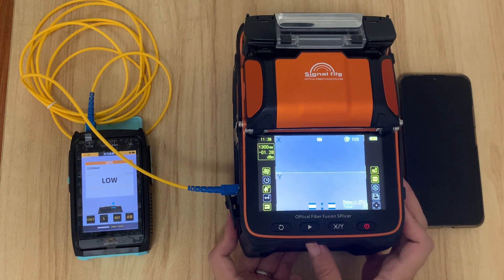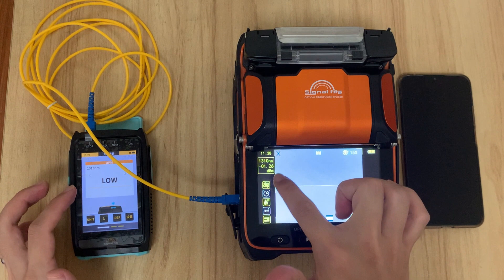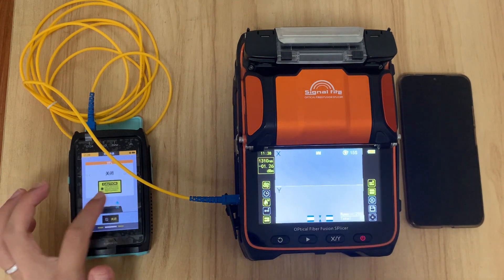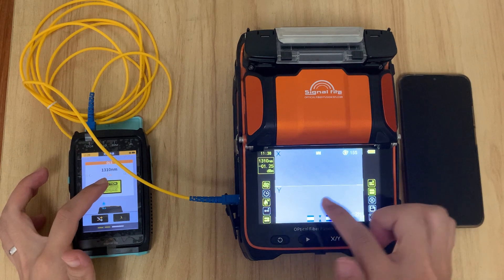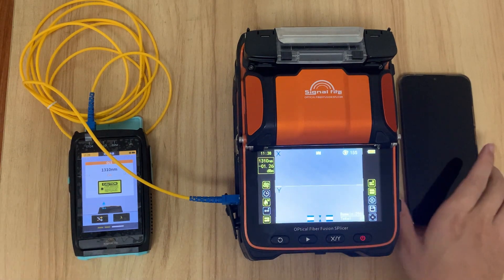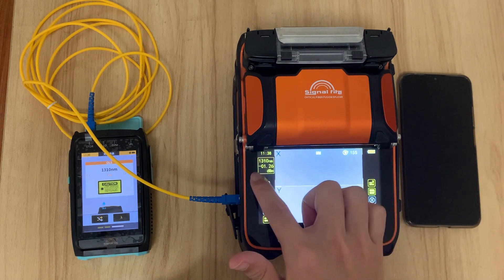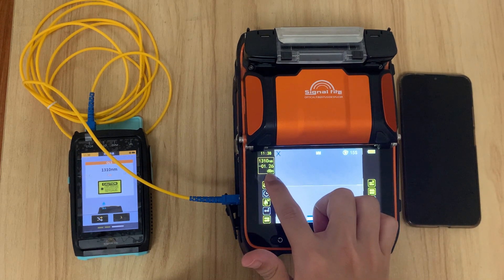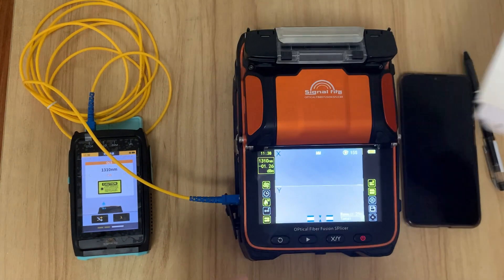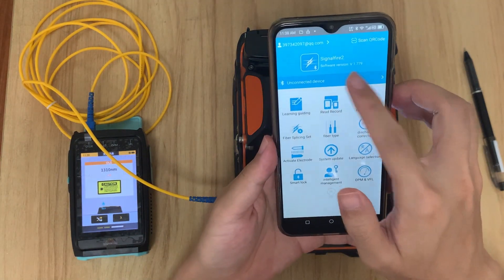We must ensure that the light source wavelength matches the test wavelength. You can see that both are set to 1310nm. The light source is reading 1.26, and the machine is also reading 1.26 — they are aligned, so we can proceed with calibration.